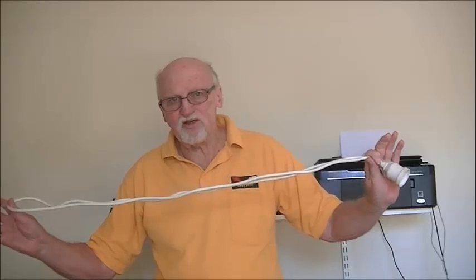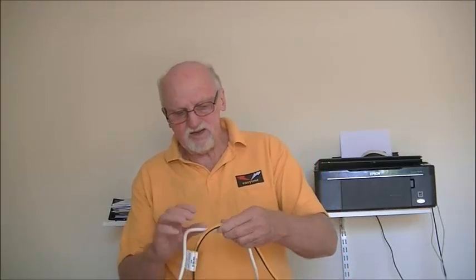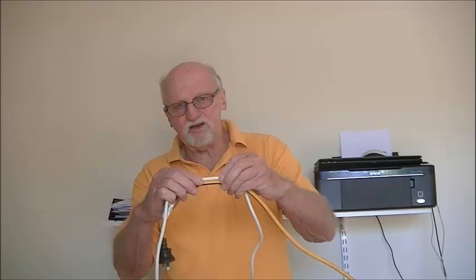So what can we conclude from all that? Firstly, the voltage drop, therefore the losses, therefore the heat in a lead is directly proportional to the length of the lead and inversely proportional to the thickness of the lead, the cross-sectional area of the conductors. You can see that is significantly larger.